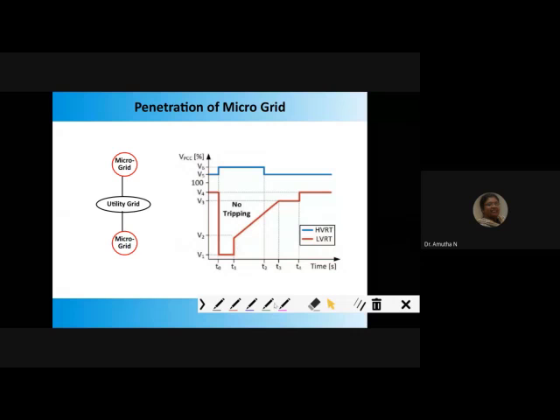Suppose the voltage during the fault is V3. It means that the fault is not that severe, but for this fault it is expected that the generators would not be disconnected for this much amount of time. From T0 to T3, it should not be disconnected. After that, it can be disconnected. So the generator has to supply the power from T0 to T3, and after that it can be disconnected. This we call low voltage ride through, and similarly it can be considered for the high voltage ride through.